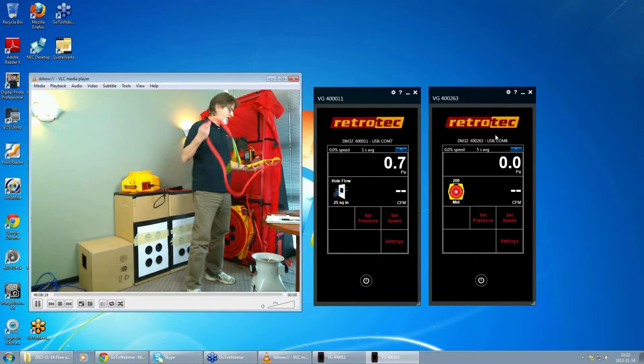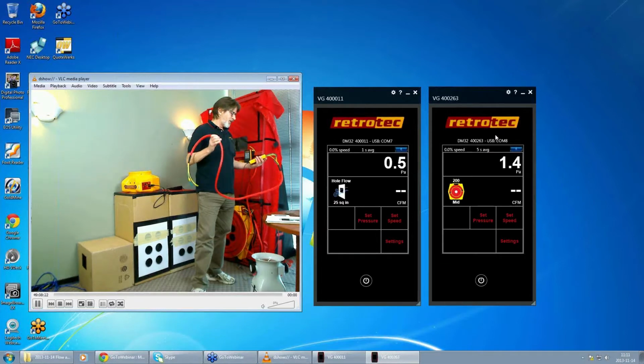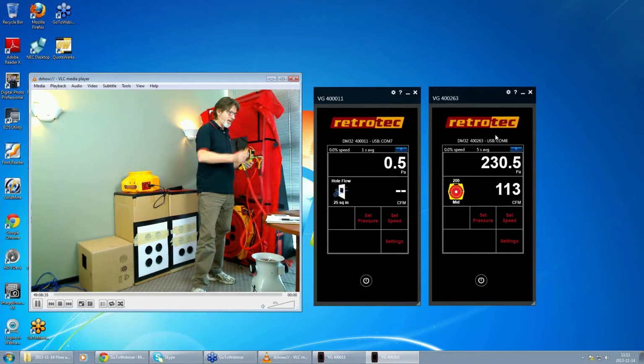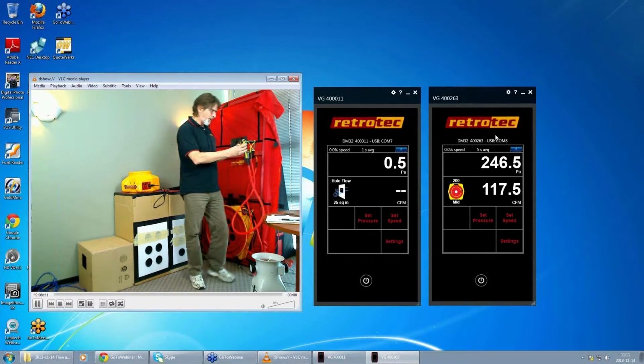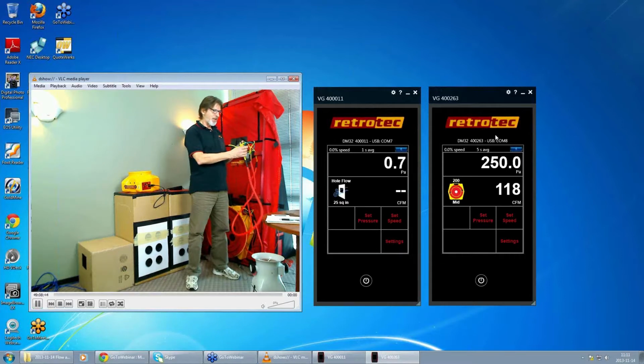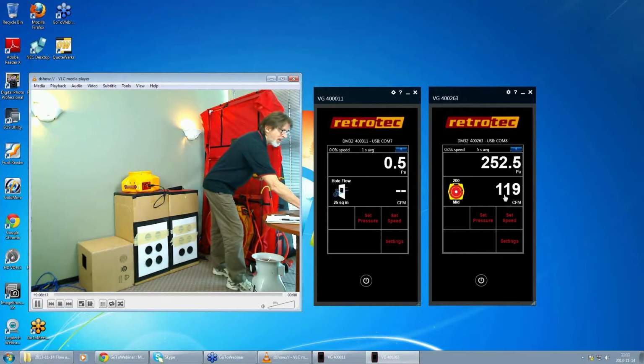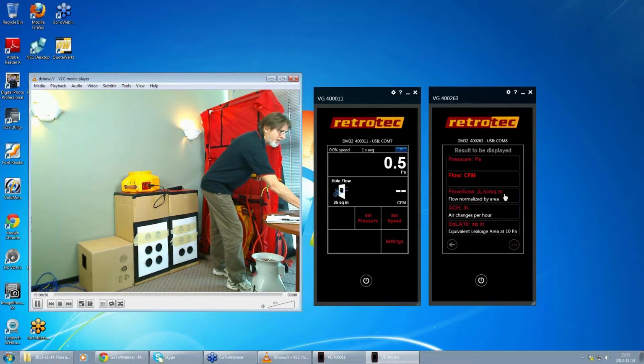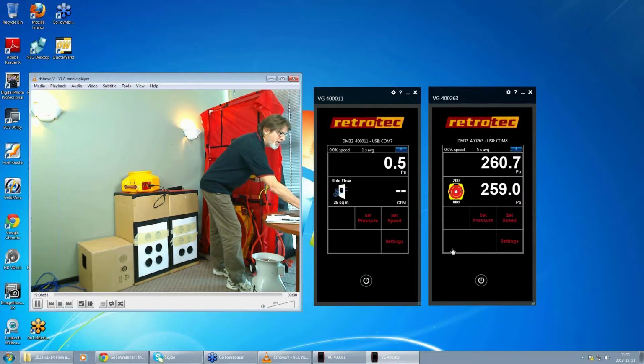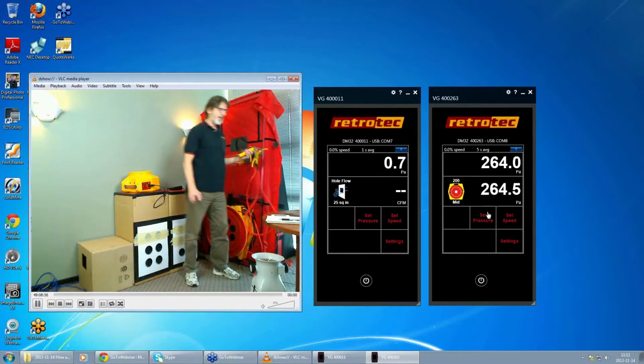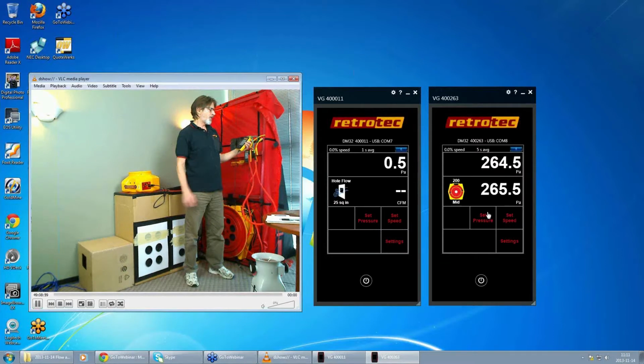So this is the umbilical that comes with this gauge, and the gauge on the screen that we're messing with is the one on the right-hand side, and you'll notice that if I was to plug the green one into the other side, I would actually get a pressure. So whatever appears on this gauge is actually appearing on the screen. The first thing I wanted to show you is how to check your gauge and check your tubes at the same time. Now, on this gauge here, we're showing CFM. So I want to compare pascals and pascals. And you notice I got 261, 262 on both channels. That indicates that the channels are reading correctly and there's no leakage between the channels.